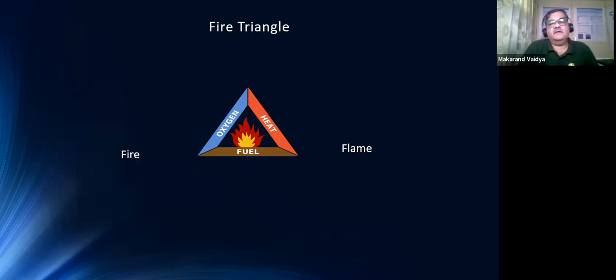In fire, I will tell you in layman's terms what is the difference between flame and fire. In fire, if you have got a detector, a flame sensor or fire sensor, that sensor monitors for no flame, and it triggers when the flame is there. In furnaces and boilers, the same sensor is used to sense the no-flame condition - that means when no flame is there, it triggers, and when flame is there, it is happy. So it is exactly the opposite, exactly the reverse thing.